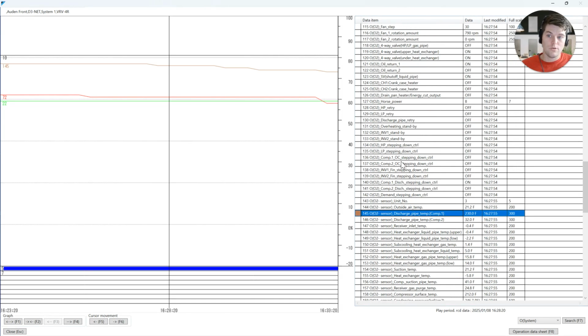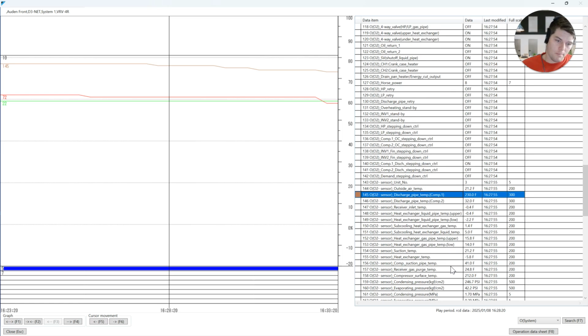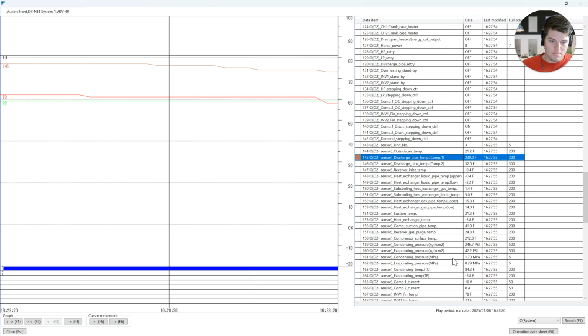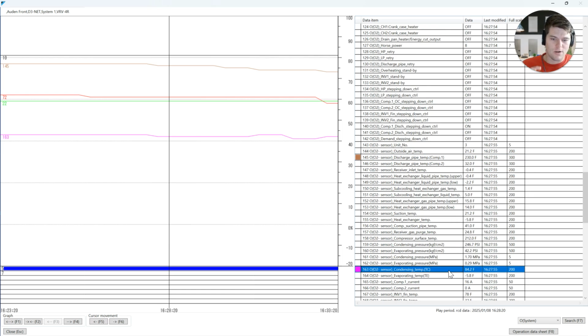So let's just do the ones that I love to see, and that's discharge superheat. How do we find discharge superheat? Discharge pipe temperature, right? Subtracted from my condensing temp. My condensing saturation temp. There's that word, saturation. Oh, it's like silk to my ears.